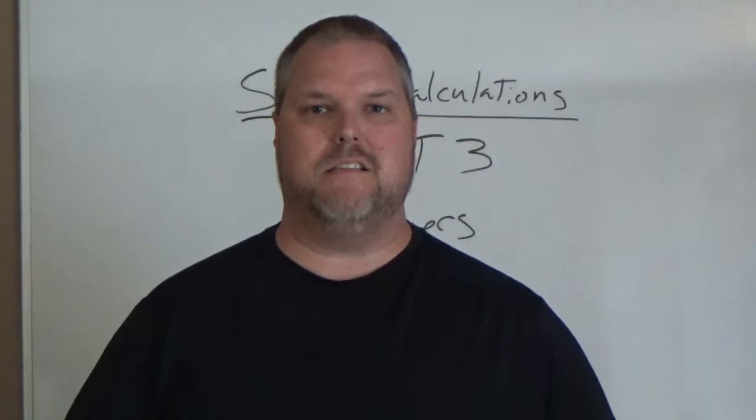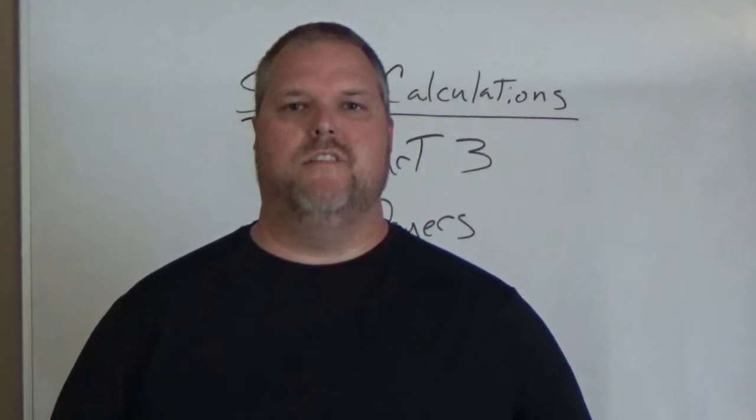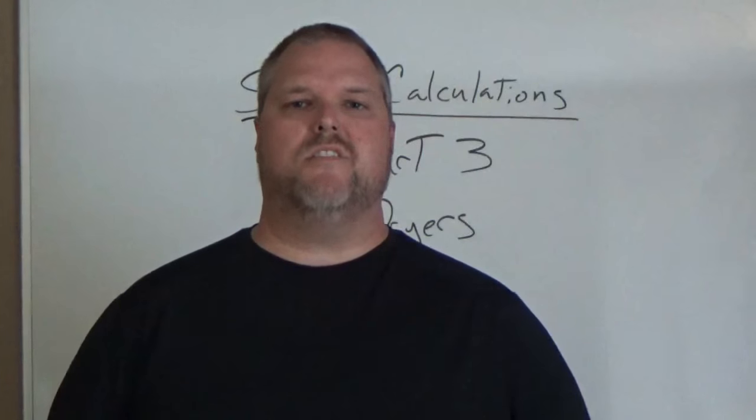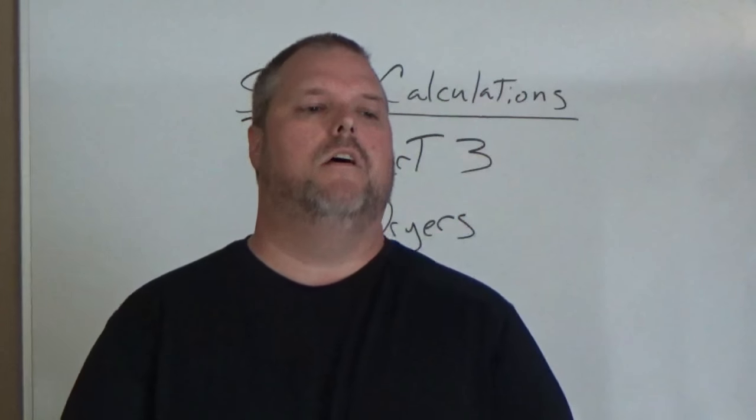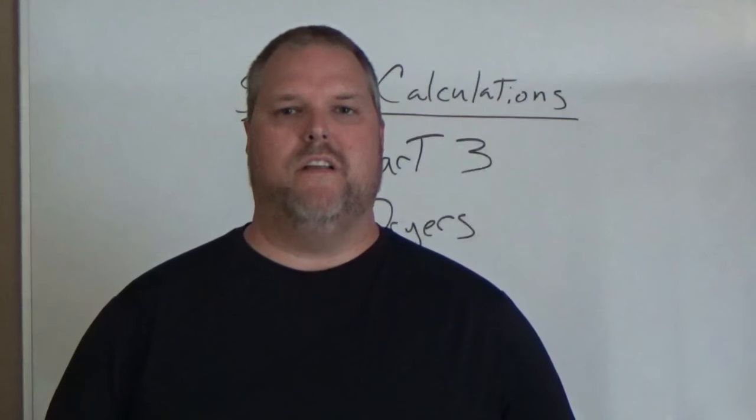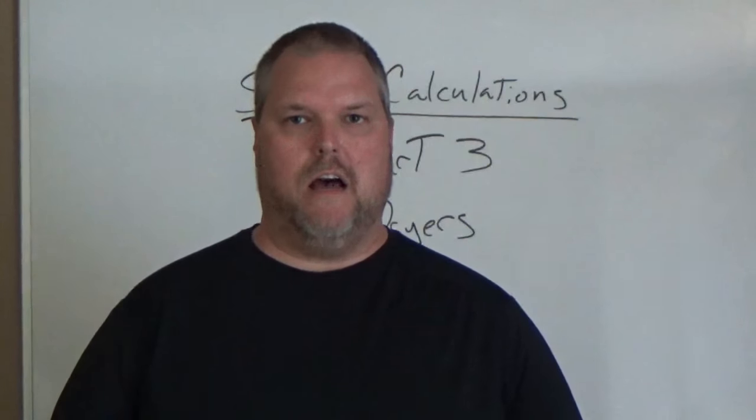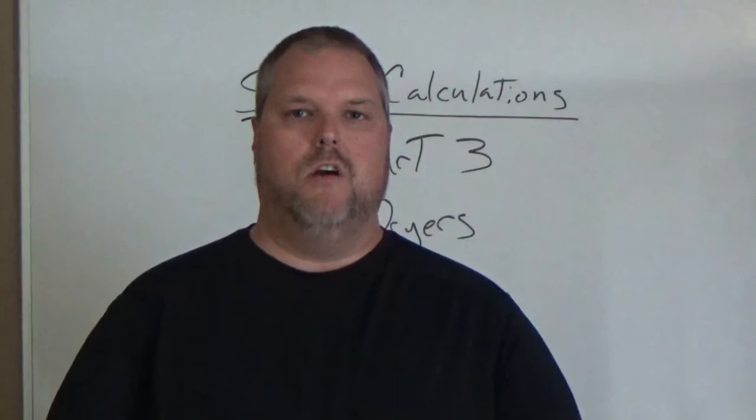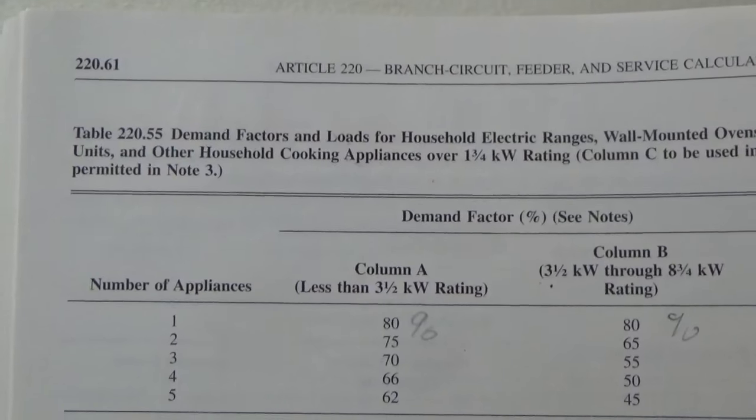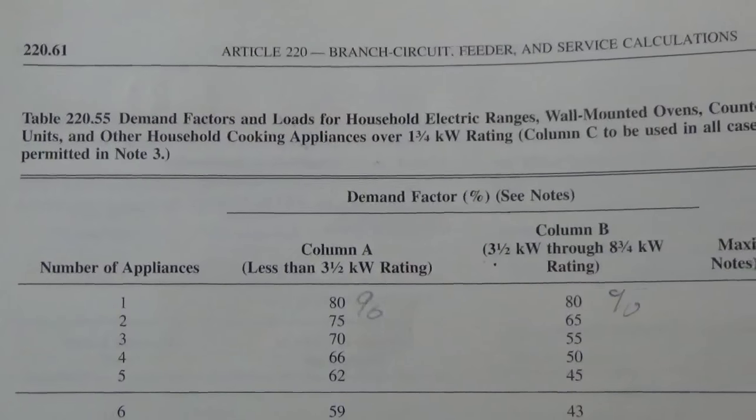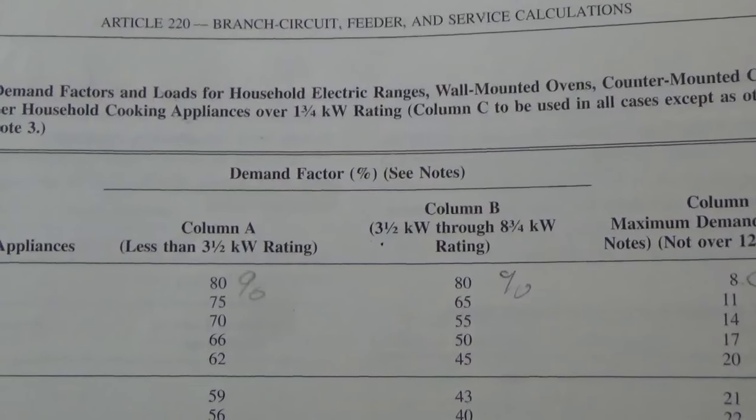In part 2 of this video, we're going to discuss ranges. Ranges is going to take up our line 12. Article 220-55, we use the table. In order to calculate electric ranges, we have to go to Table 220-55, which gives us our demand factor in percentages.